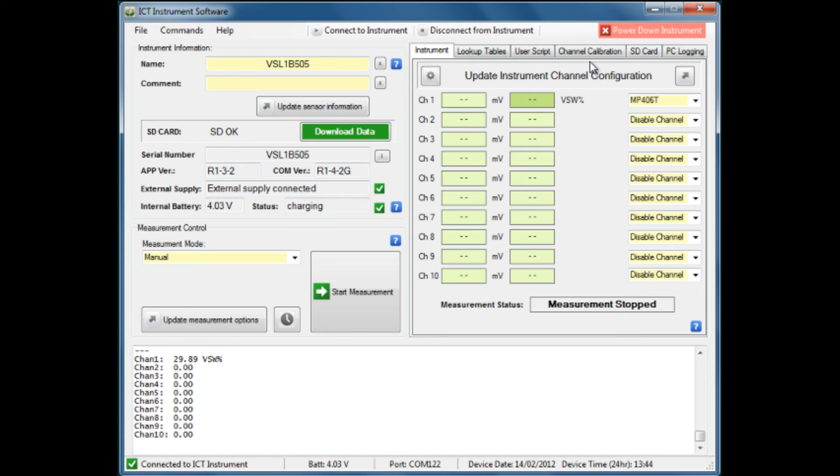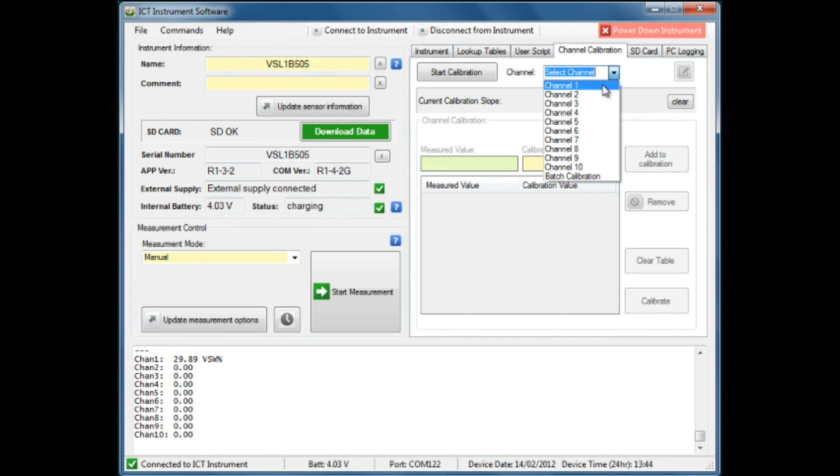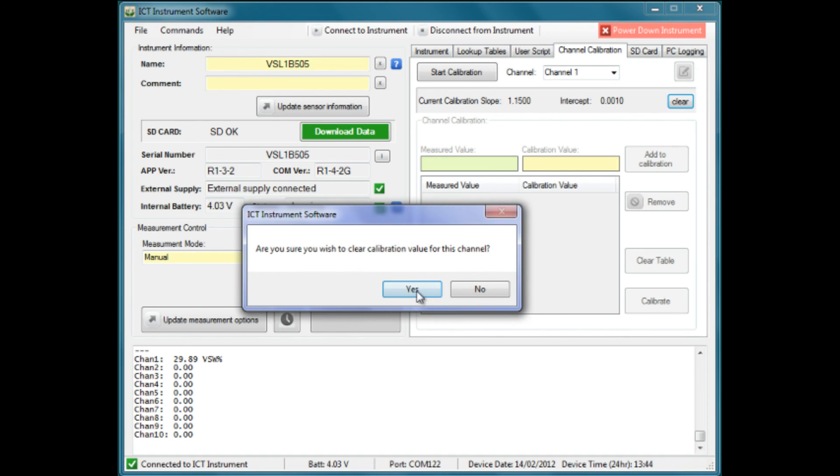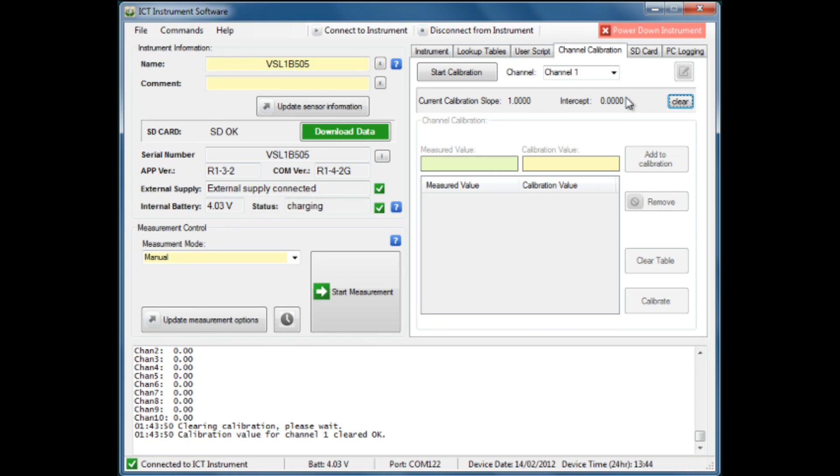We go to the calibration section and select channel 1 as the channel we intend to use. We notice that there is a calibration slope, which is a factor that applies a correction value to the results. We don't wish to use that, so we will clear it. We confirm that yes, we intend to clear that, and the calibration has been removed from channel 1. We're ready to do a fresh calibration.